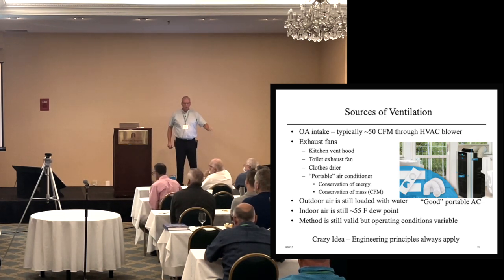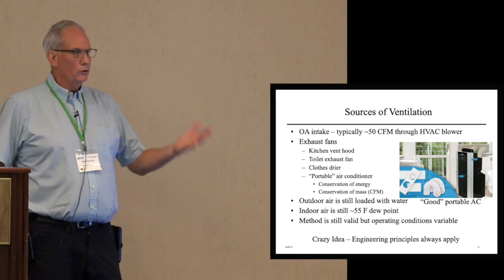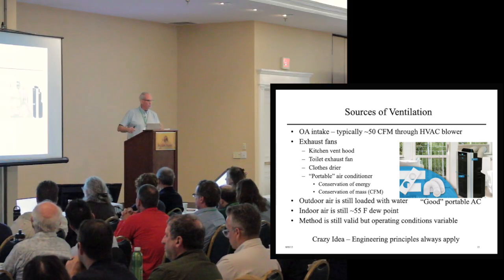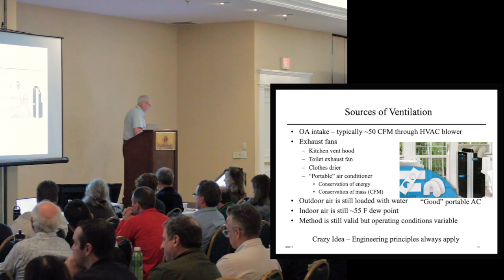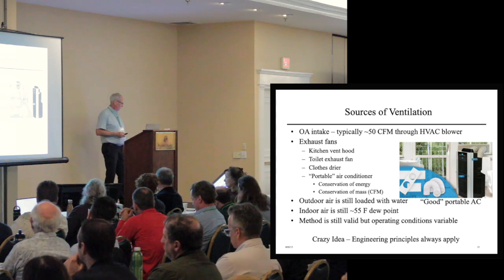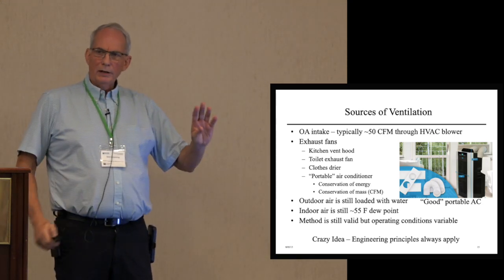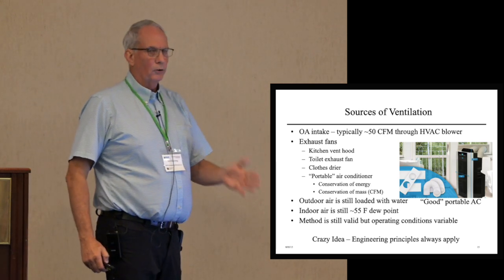Okay? So, trying to make at least some parts of my presentation positive, I put a picture of a good portable air conditioner. How do I know it's good? It has both intake and exhaust. Okay? Let me point out, in these humid climates, that outdoor air is loaded with water. Round numbers, in this environment, there is twice as much water in the outdoor air as what we want inside. Okay? That's a lot of water. We still need that 55 degree dew point because we're still aiming for the 74, 75 degree, 50% humidity point. Okay? So, I had this crazy idea. I hope it doesn't offend too many people. Engineering principles always apply.